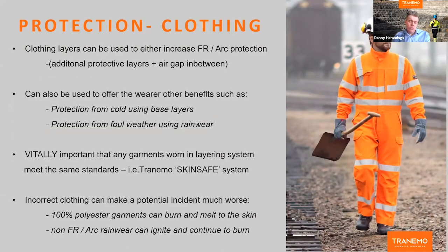There also, then, when you're trying to achieve protection, sometimes it may be that the protection offered by a single layer garment won't be enough for the incident energy that needs to be dealt with. So what we can do there is we can put clothing layers into combination, and therefore increase the protection that's offered, both the intrinsic FR protection, but also the protection offered in terms of resistance to thermal energy.